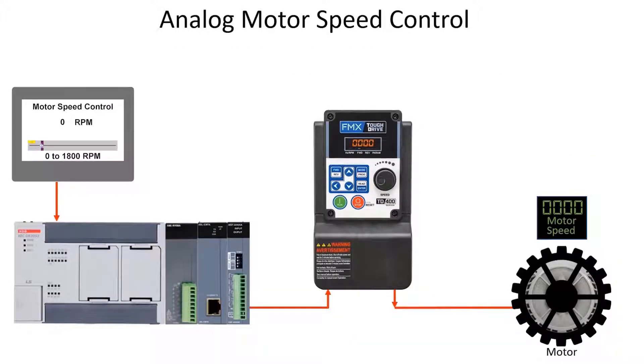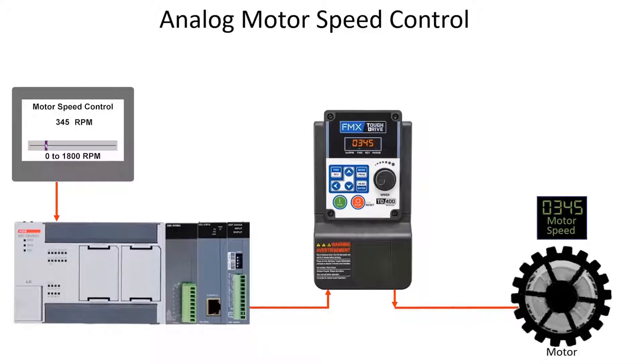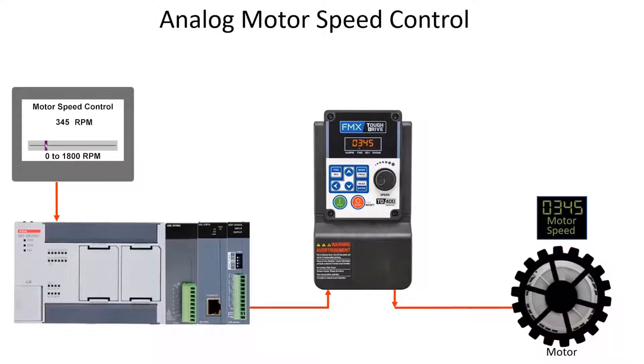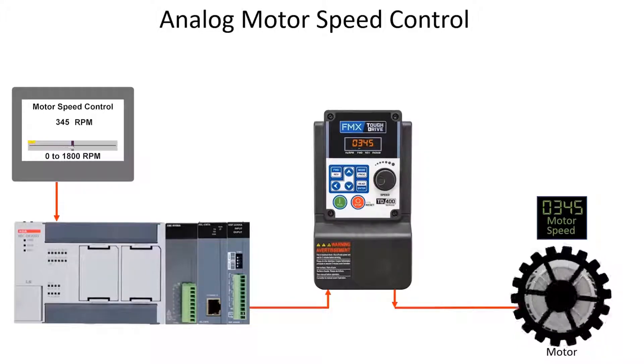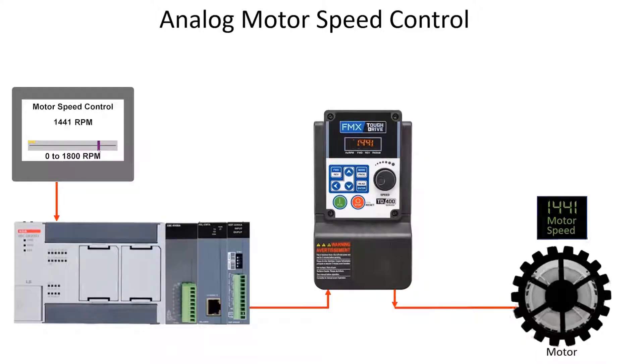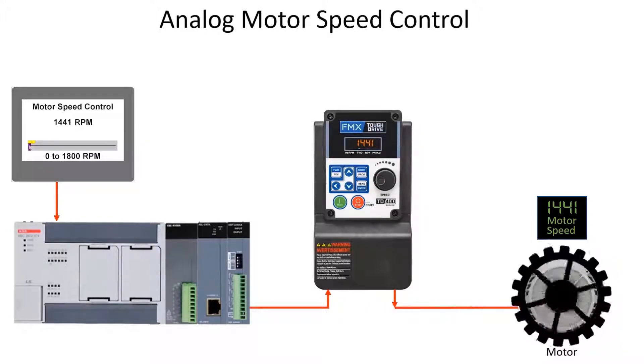To summarize, a speed command is entered with the operator interface. Ladder logic scales the motor RPM value to an analog voltage. This voltage is output from the PLC analog output to the VFD. The motor speed is controlled by the VFD based on the analog voltage from the PLC.